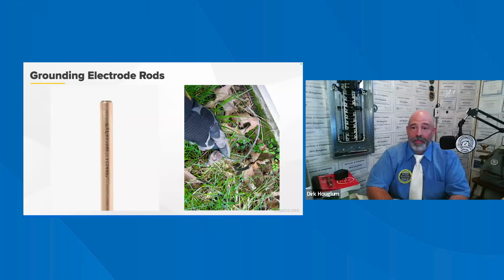If visible, you may be able to confirm the diameter by looking at the listed markings, which may indicate the rod complies with the diameter required by the National Electrical Code. The listing agencies are the CSA, the ETL, the MET, and the UL. Marks on it greater than 1/2 inch in diameter will have the correct minimum amount of coating. All rods and pipes should be driven at least 8 feet into the earth.